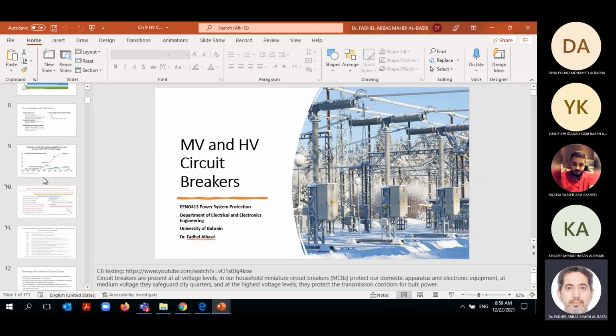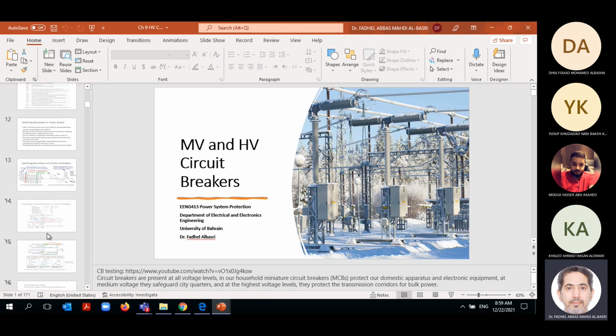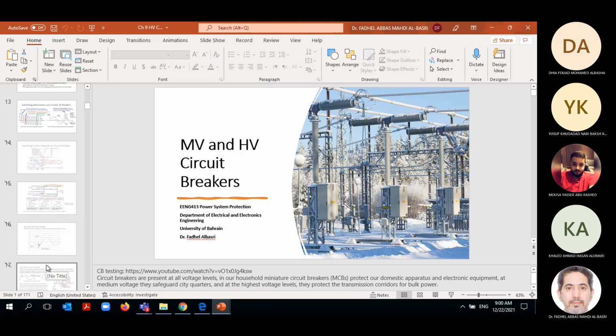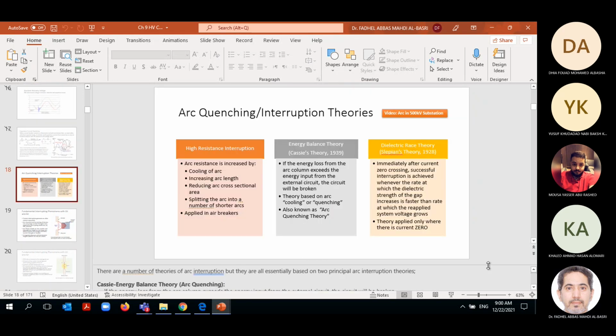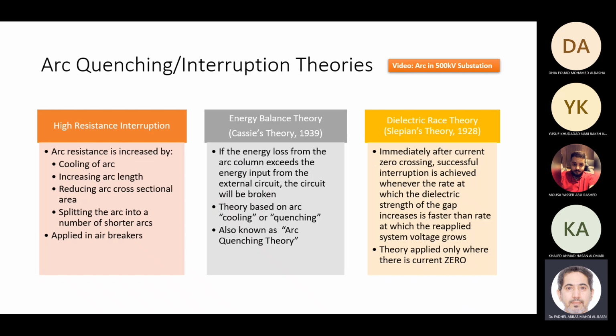So how do we get rid of this arc? We have different principles. I tried to skip some of the slides because it's too long. So the arc quenching theories, we have roughly many theories. How do you get rid of this arc? We can use the high resistance interruption principle, where we increase the arc resistance so that the current decreases and becomes zero.